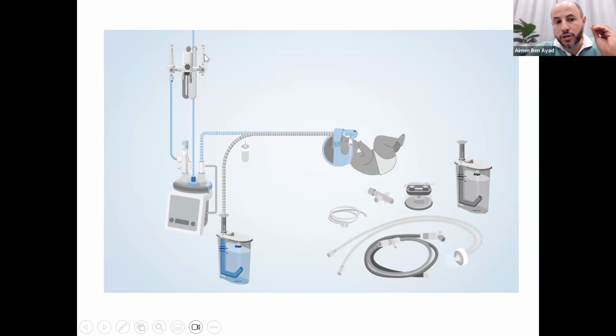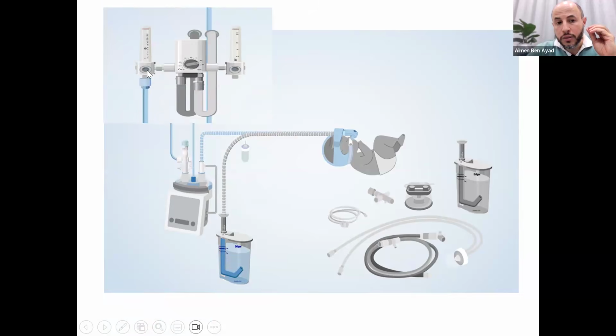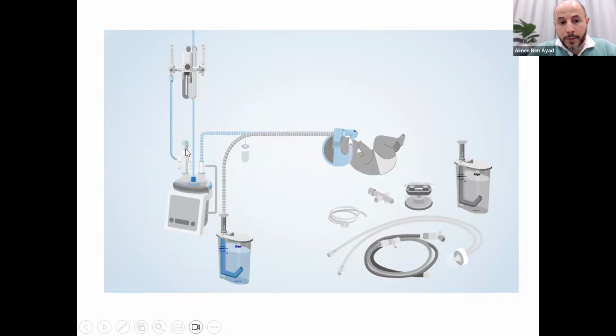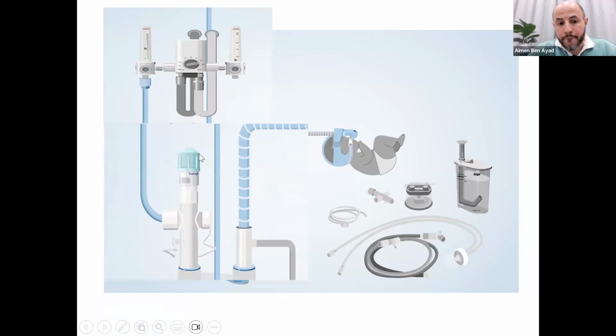What you need is a source of oxygen and a blender to control oxygen. So flow, 100%. You can control the flow, how many liters per minute. It comes to the blender, or opposite, from the wall, comes to the blender, and then you control how much flow you want to come out. Okay? And then it goes to pressure. How much you sink inside here, the water. The more you sink inside, the more pressure you will generate. So here, numbers 5, 6, 7, 8. The deeper you dig, the higher the pressure you will generate.